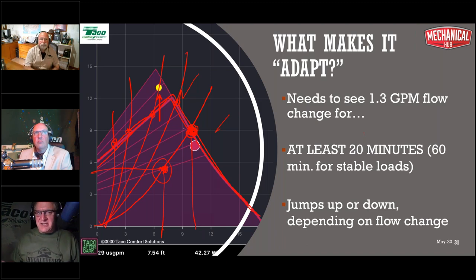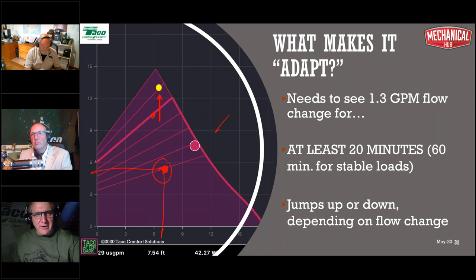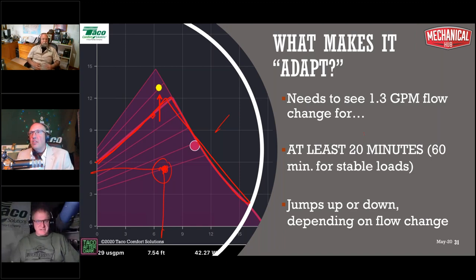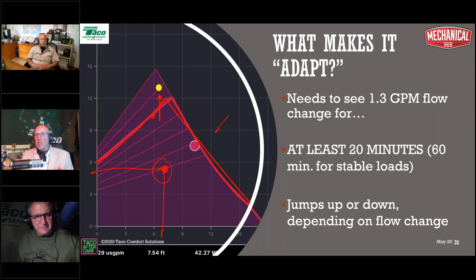I'd say 95% of the time, if you put this on a zone valve system and you put it in Active Adapt, you will never get it to operate anywhere but here. I absolutely believe that. I don't think it'll ever work anywhere but on that line, because when it shuts off, it goes right back to that line. Now it will vary in speed and you'll see the watt draw change. Yes, absolutely. So you're going to assume that it's learning something. It's just operating like a zone valve system.